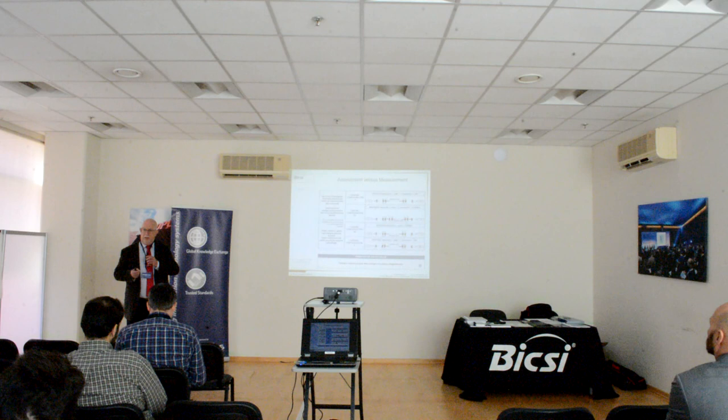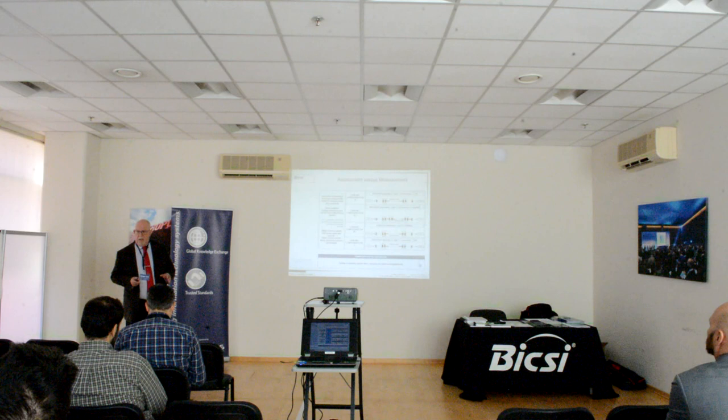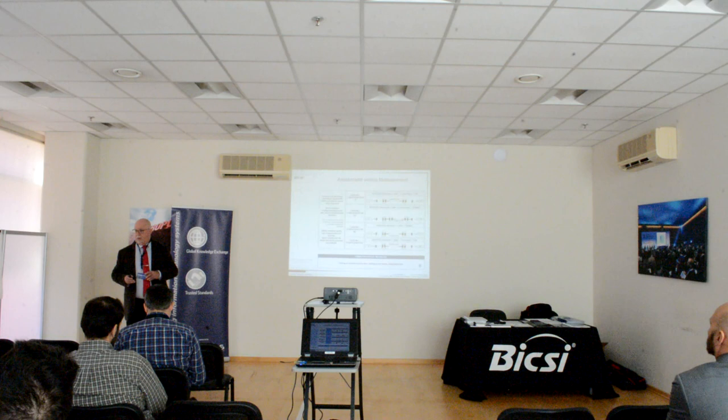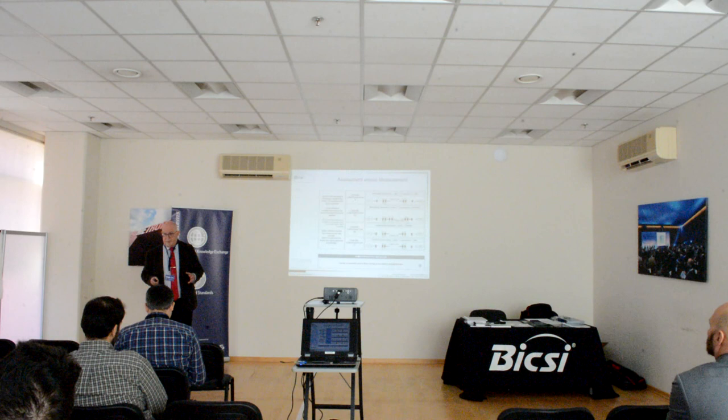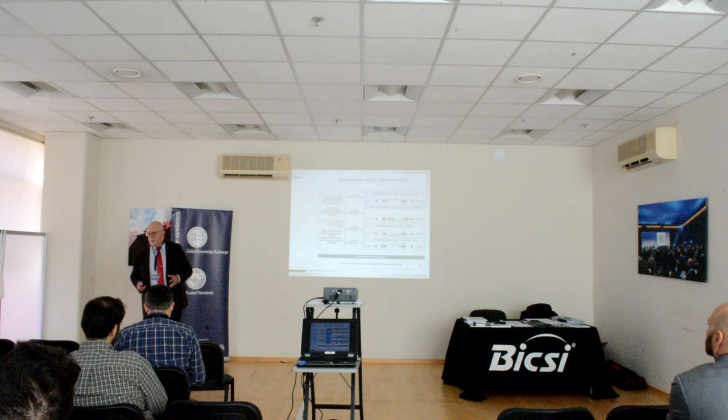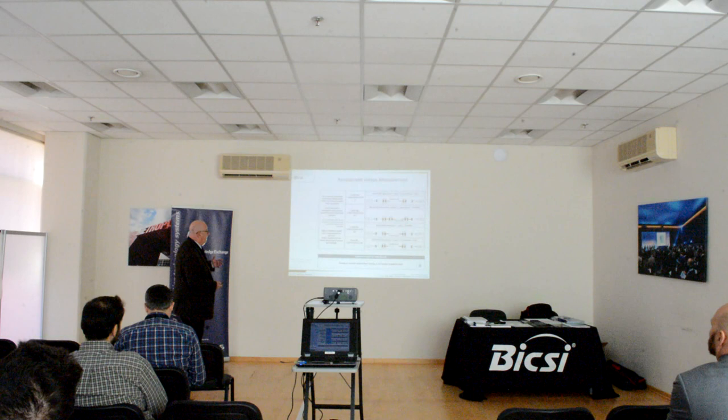Because in the middle of the 2000s, cheaper power meters came with a fixed connector. Could have been an SC, could have been an LC. It was a fixed connector. And if you've got a fixed connector on your power meter, which isn't the same as your cabling, or certain parts of your cabling, then you can't use the appropriate method. So you'll end up using a different method, which again changes the results and changes the limits. And then you're actually assessing something rather than measuring it.